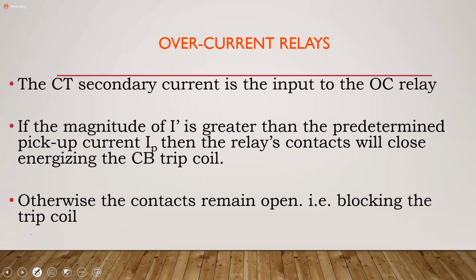So if the magnitude of your current is greater than the predetermined pickup current, then the relay contacts will close, and it energizes the trip coil for your circuit breaker. If it does not reach that value, the contacts will remain open, and the trip coil will not be energized. So again, go back to the diagrams that I sent you yesterday. I hope everybody had access to them and you're following me with these.